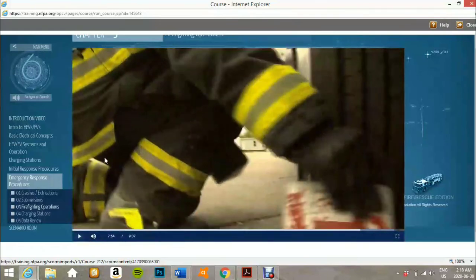Firefighters should follow proper procedures - batteries that reignite usually are from damage and from not being cooled enough. So we don't want to just bring it to room temperature, we want to bring it to room temperature and monitor. If that temperature starts to rise spontaneously, that indicates an issue with the battery pack and we want to continue to cool.